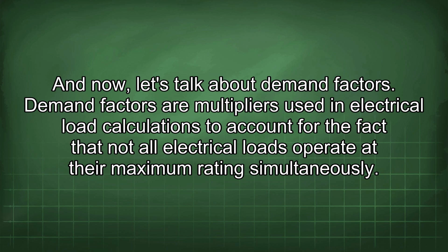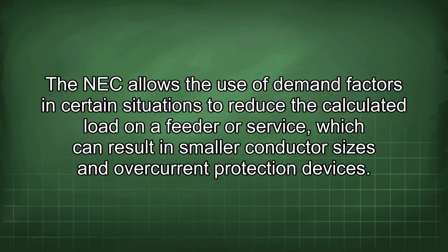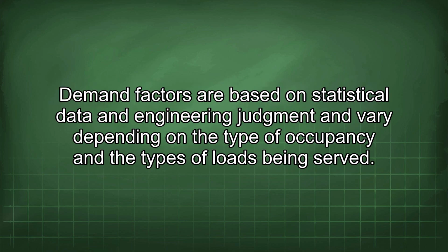Demand factors are multipliers used in electrical load calculations to account for the fact that not all electrical loads operate at their maximum ratings simultaneously. The NEC allows the use of demand factors in certain situations to reduce the calculated load on a feeder or service, which can result in smaller conductor sizes and overcurrent protection devices. Demand factors are based on statistical data and engineering judgment and vary depending on the type of occupancy and the types of loads being served.